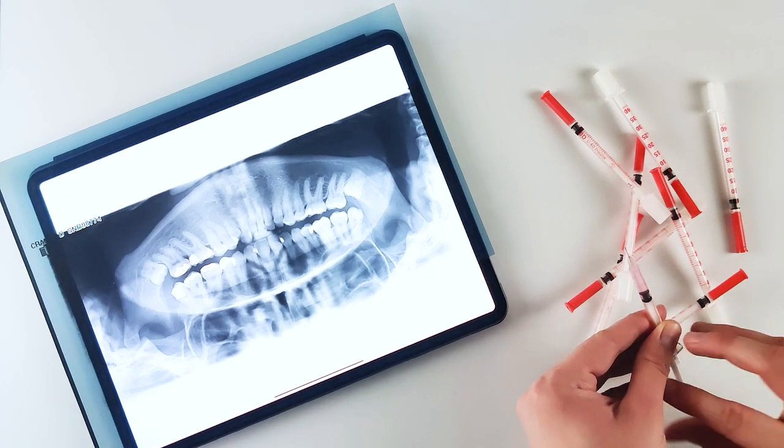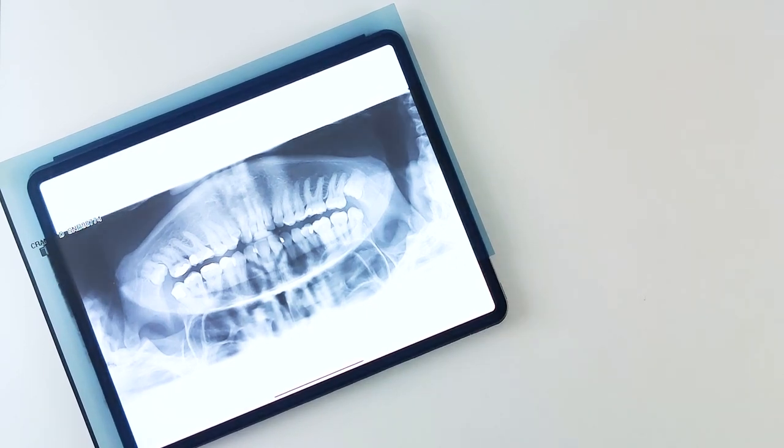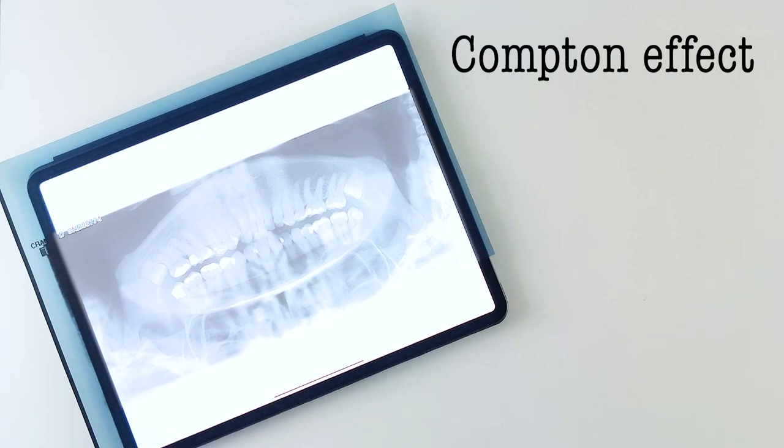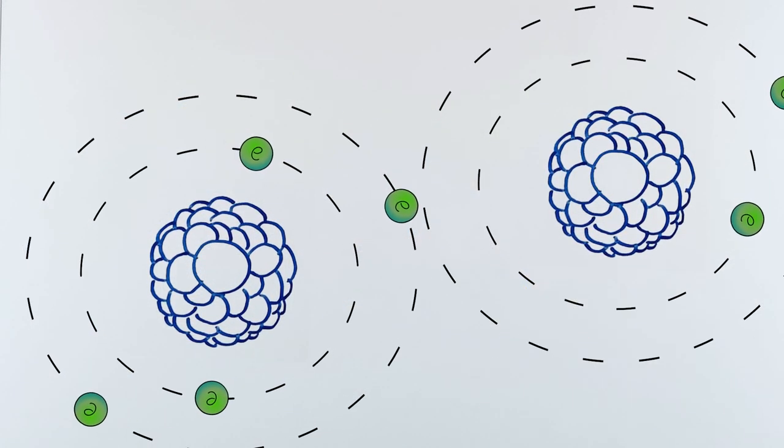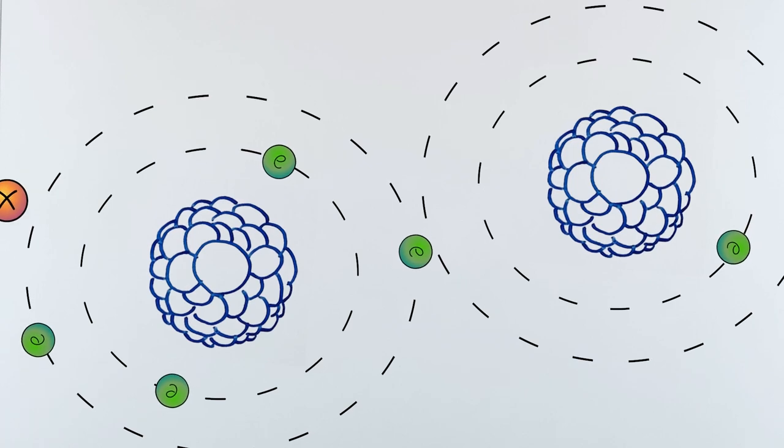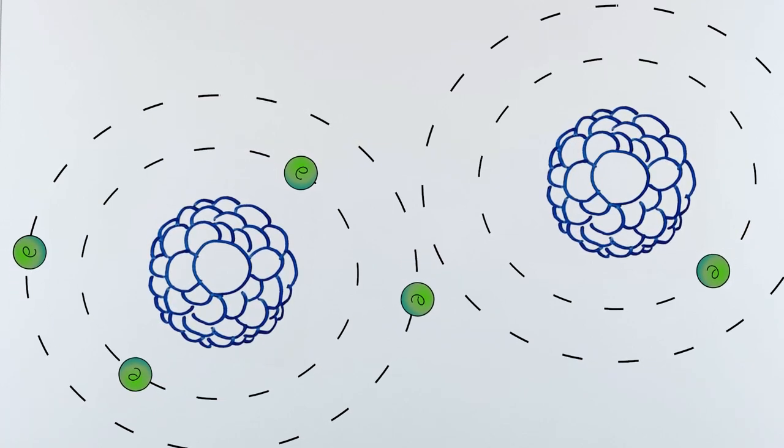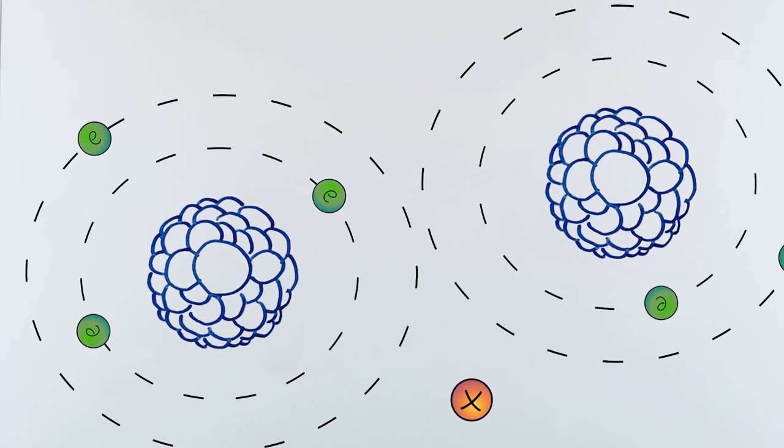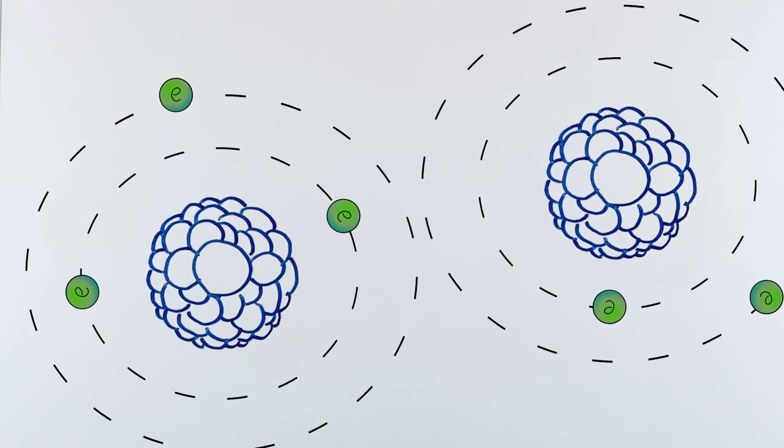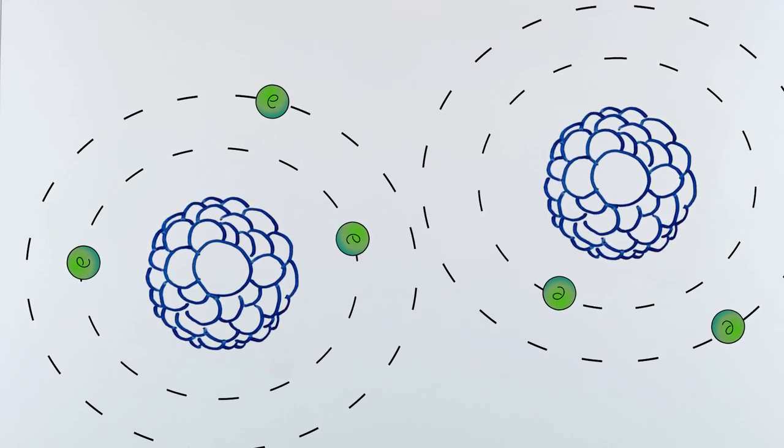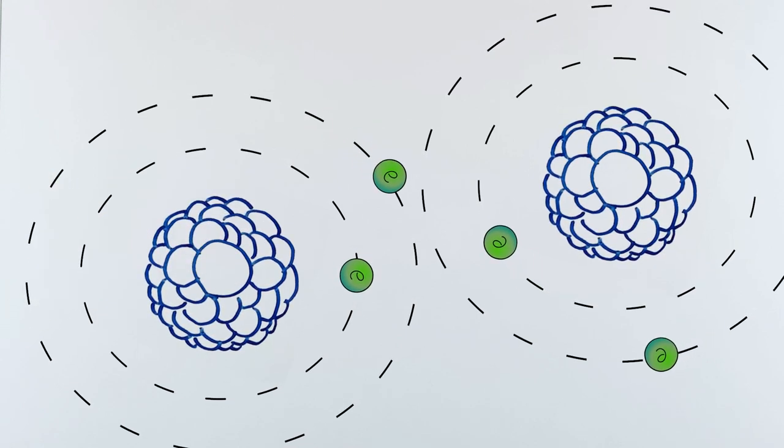But let's get back for a moment to the way of recording the image, because a picture recorded directly on the film very often looks really foggy. This is because of Compton effect. Sometimes, instead of being absorbed or just flying through the body, a rebellious photon collides into an electron and ejects it. Afterwards, the photon turns and hits the film where it should not. As a result, the film is slightly blackened in random places. It may be very misleading for the physician looking at an x-ray image. So how to get rid of the beam that causes blur?